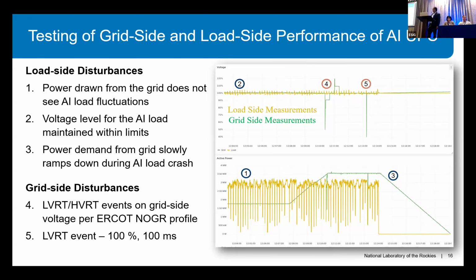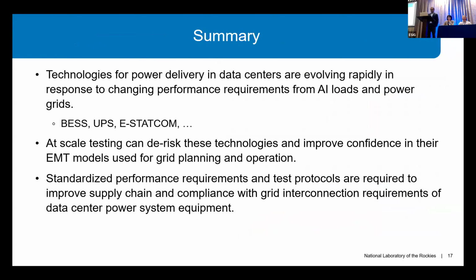And then here, events 4 and 5 represent some grid voltage disturbances, low voltage ride-through, both low voltage and high voltage. The second event, number 5, is actually a very severe 100% voltage dip event. Again, we are seeing that the UPS is able to bring back the grid demand in a very short duration, and at the same time, the load doesn't see this disturbance.